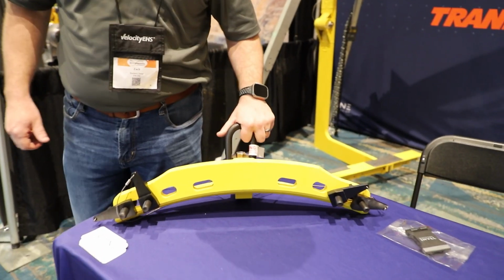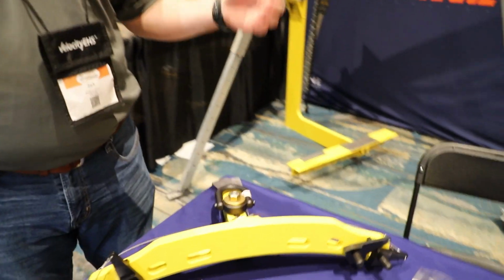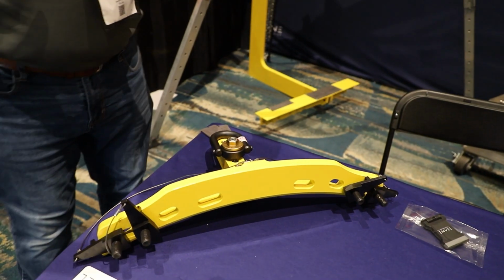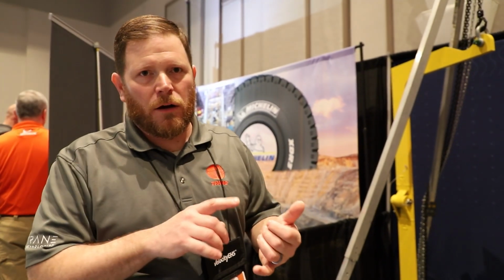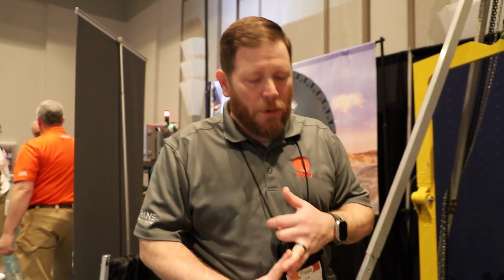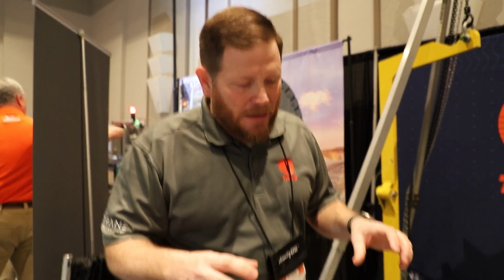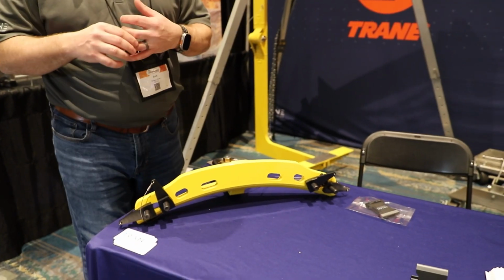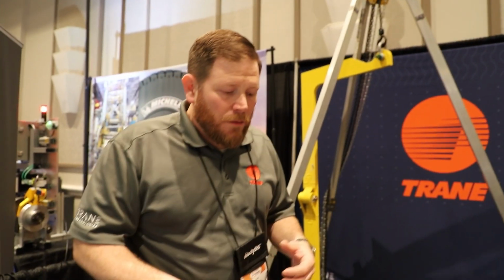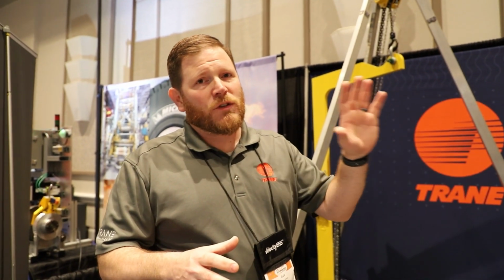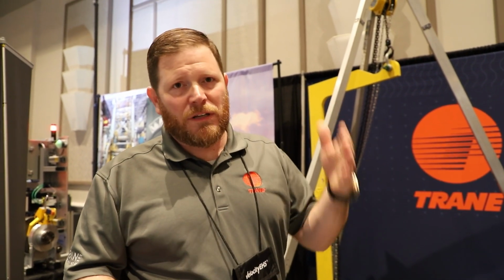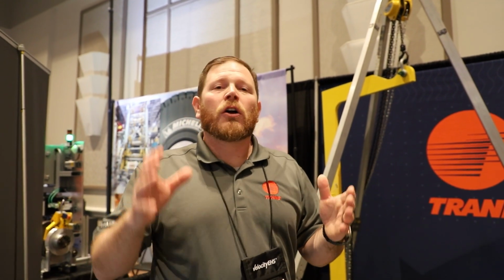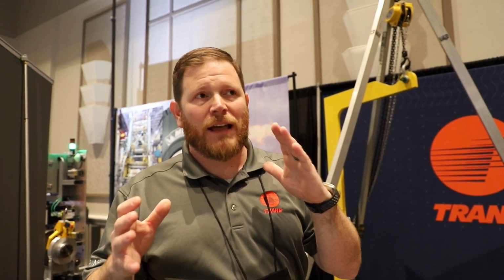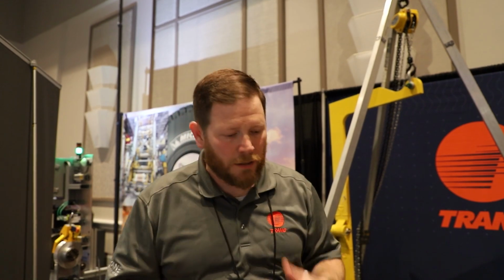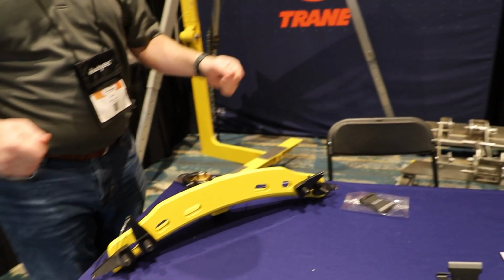This is called our suction cover lifting bracket. On our Trane water-cooled centrifugal chillers, one of the components that comes off anytime we're doing a scheduled teardown or any sort of repair is our suction cover. The suction covers can be up to around 1,400 pounds depending on the size of the cover itself. Anytime the suction cover goes off and back on, it has to be perfectly perpendicular, but the center of gravity on the suction cover causes it to tilt on a severe angle that the techs have to struggle with when removing and reinstalling it.